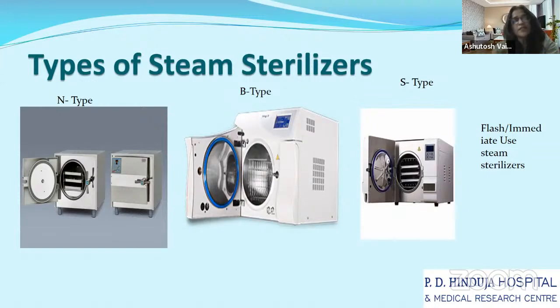So basically, flash sterilizers, or immediate use sterilizers, are the sterilizers which are supposed to be used immediately. During a procedure, if anything falls down or becomes unsterile, and you want to sterilize it, you just put it in this immediate use sterilizer, sterilize it without any wrapping material, and use it immediately. That's why the nomenclature has changed to immediate use steam sterilizer.